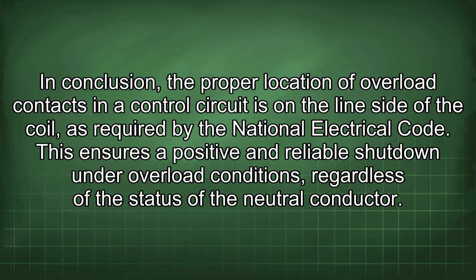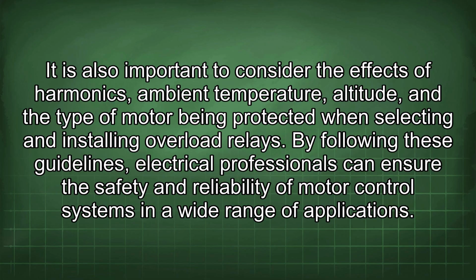In conclusion, the proper location of overload contacts in a control circuit is on the line side of the coil as required by the National Electrical Code. This ensures a positive and reliable shutdown under overload conditions, regardless of the status of the neutral conductor. It is also important to consider the effects of harmonics, ambient temperature, altitude, and the type of motor being protected when selecting and installing overload relays. By following these guidelines, electrical professionals can ensure the safety and reliability of motor control systems in a wide range of applications.